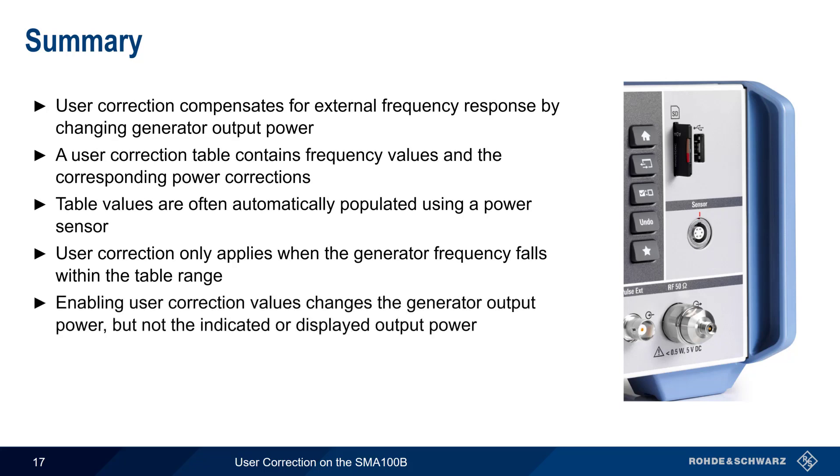And lastly, even though user correction values will change the generator output power level, the indicated or displayed output power in the SMA GUI does not change when user correction is activated.